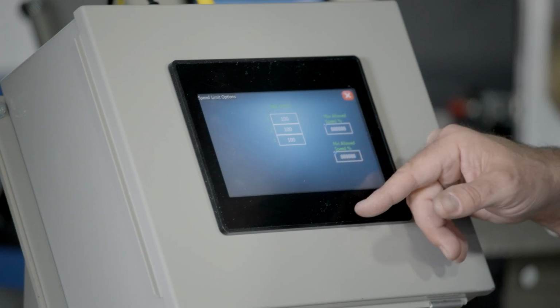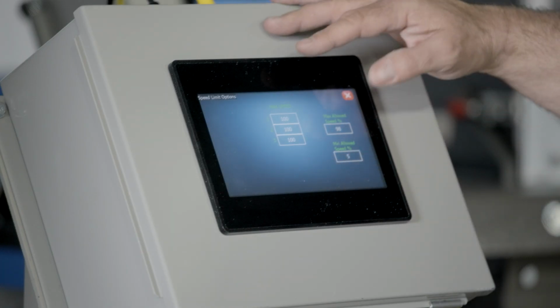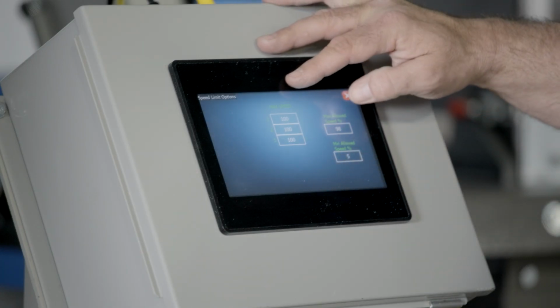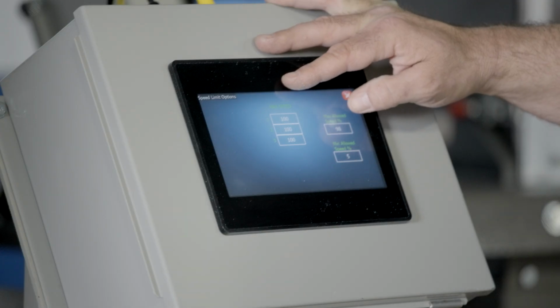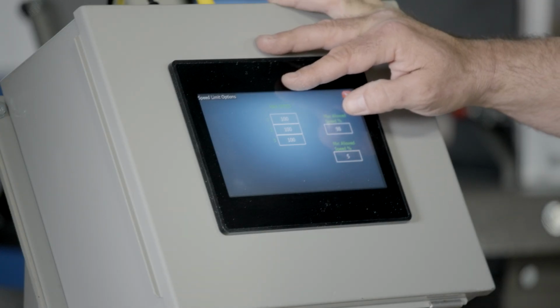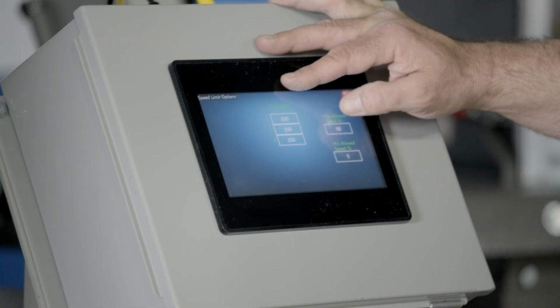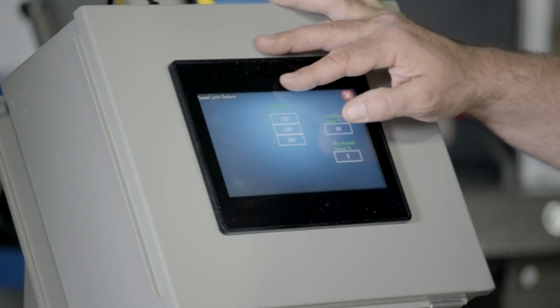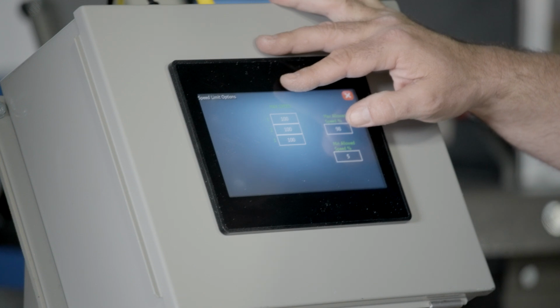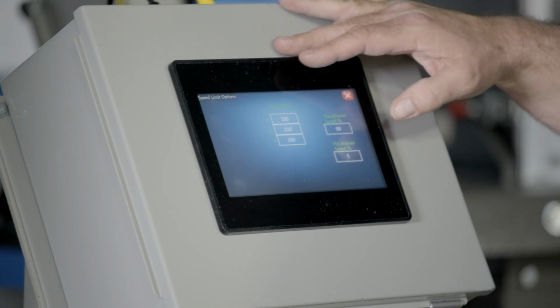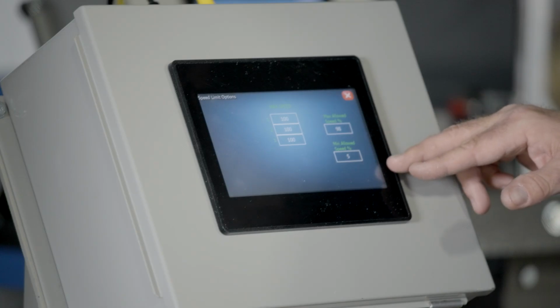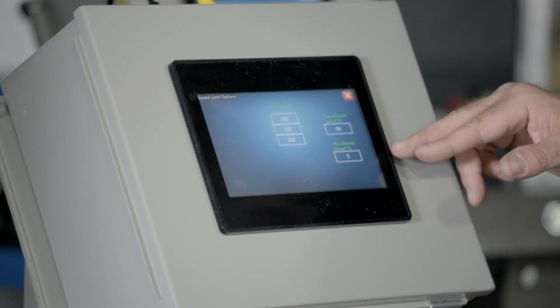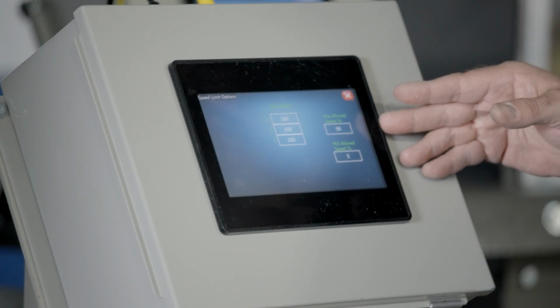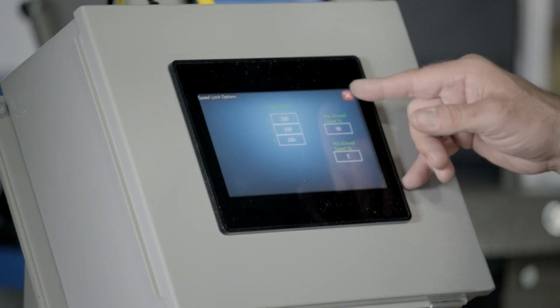Next button down here is motor speed limits. So we have a max speed of 100 set. We don't use closed loop feedback since we're using AC drives and they're 100% linear. We don't need to look at speed feedback. We just know that when we send 5 volts out to the motor, it's going to go half speed. When we send 10 volts out, it's going to be full speed. And then we limit the speed between 5 and 98% so we don't trip the motor out on overcurrent from running too slow or too fast.